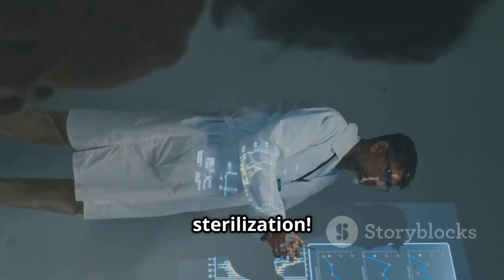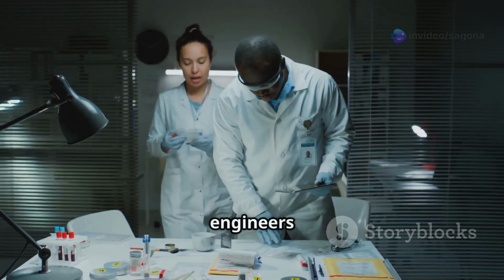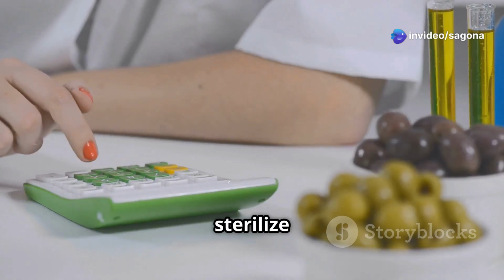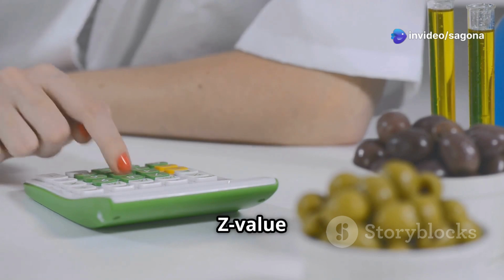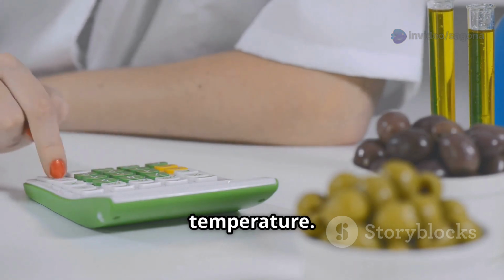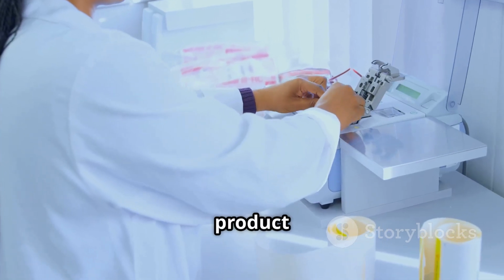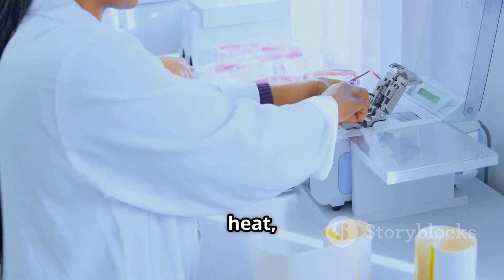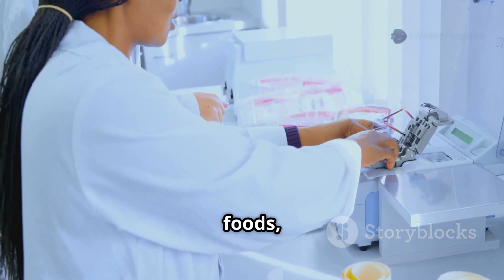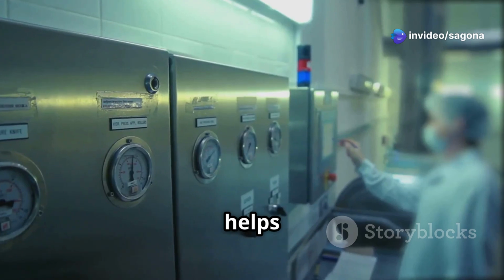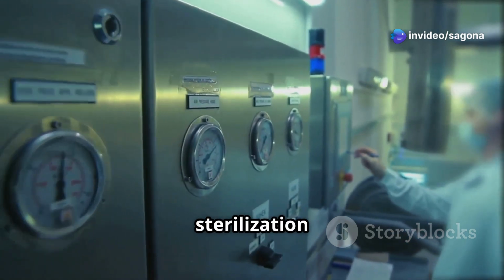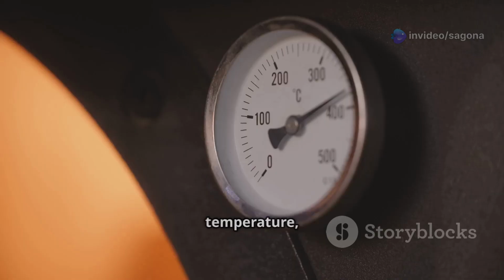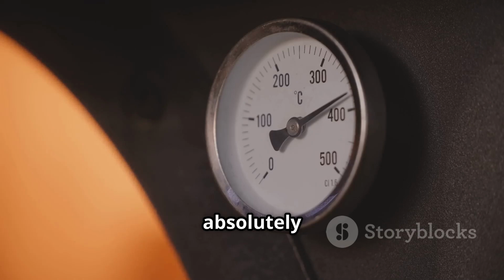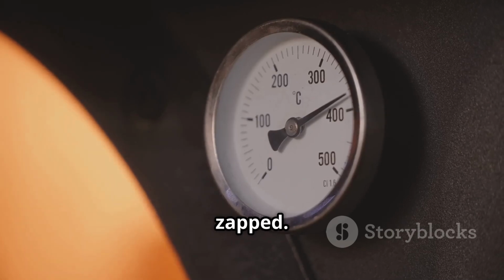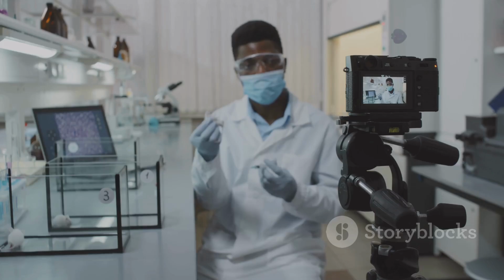Knowing the Z value is like having a secret power-up for sterilization. It helps scientists and engineers to be flexible. If they need to sterilize something really quickly, they can use the Z value to figure out how much to increase the temperature. Or if they have a product that might be damaged by very high heat, like some medicines or foods, they can use the Z value. It helps them calculate how much longer the sterilization process will take at a lower, safer temperature, while still being absolutely sure all the harmful germs are zapped. It's all about smart science.